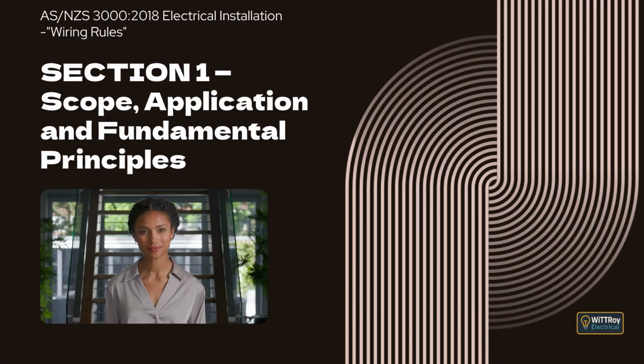Next, a protective device, like a circuit breaker, a fuse, or an RCD, must disconnect the circuit fast enough. If the touch voltage becomes unsafe, the device automatically trips and removes the supply. For this to work properly, the earth fault loop impedance must be low. That means the fault current must be high enough to operate the protective device within the required time.